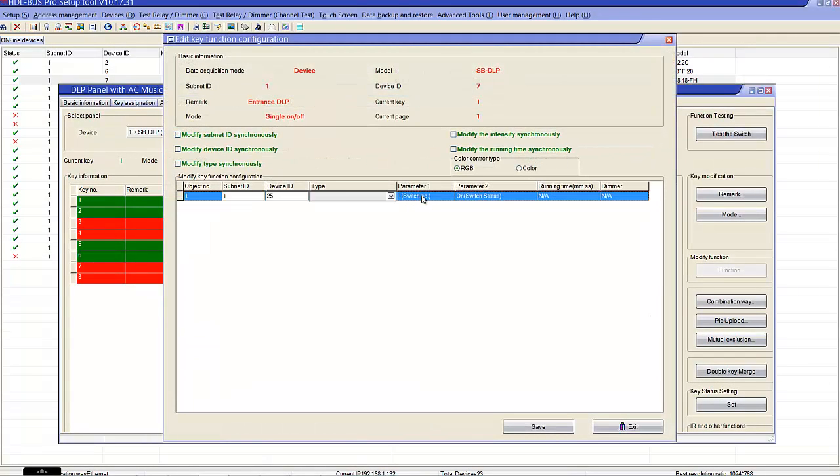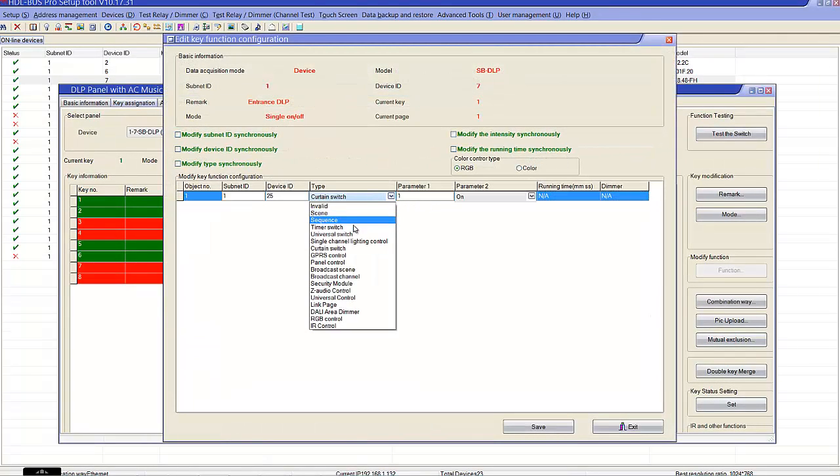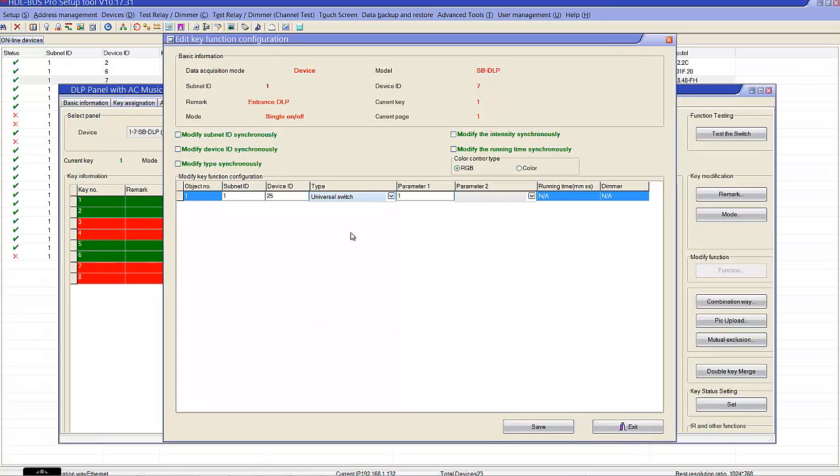Universal switch built-in is called curtain universal switch, that is 254. Whenever you use this universal switch, it triggers in a sequence: up, stop, down, stop, up, stop, down, stop, in a circle. So always use this universal switch.